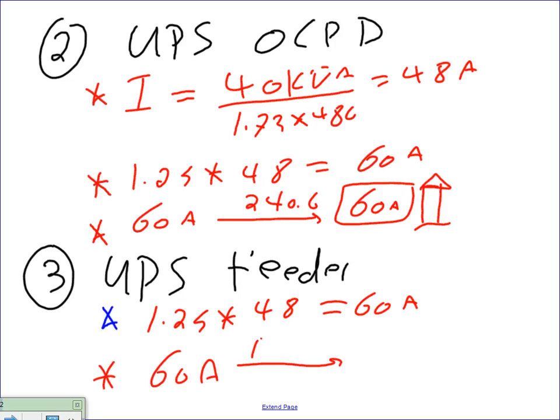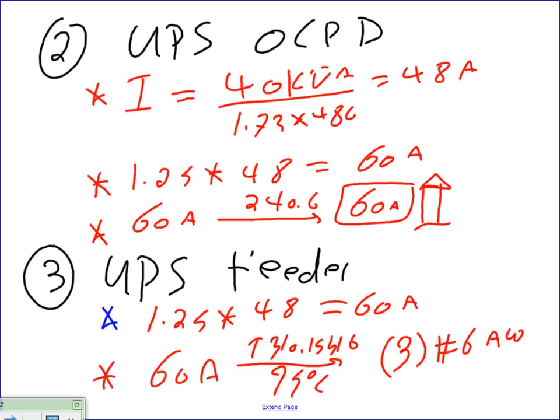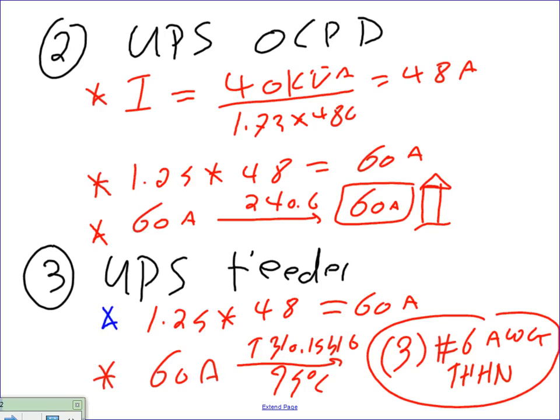to table 310.15B16 on the 75-degree column. If you took that one, it will give you, where am I here, chats? 3 conductors. How many conductors? 3 conductors. Number 6 AWG, THHN, most likely THHN. Why 3 conductor, Chris? Because I'm not bringing a neutral to the UPS. No need to bring a neutral.